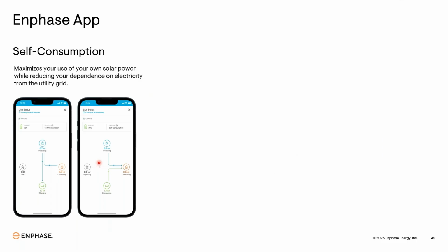So if you set the self-consumption profile, inside it you have an option for how much battery you want to drain out. If you keep your SOC level at 40%, then until 40% your house loads will run on your solar and your battery itself. If the load exceeds, only in that case it will import from the grid, otherwise it will only work on solar and battery. But if batteries go below 40%, it will automatically come into a charging mode. Your battery starts charging, because you need some power for emergency purposes also, during off-grid conditions, also 40%. So this is the self-consumption profile.